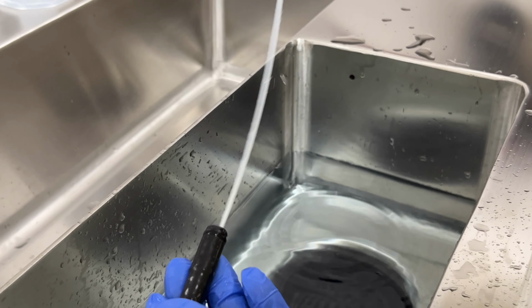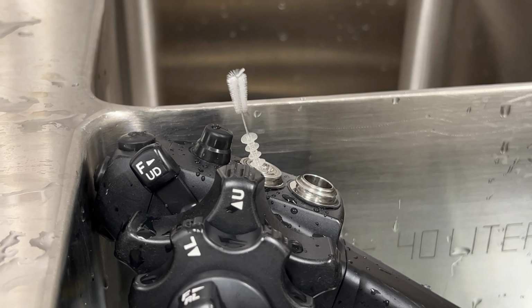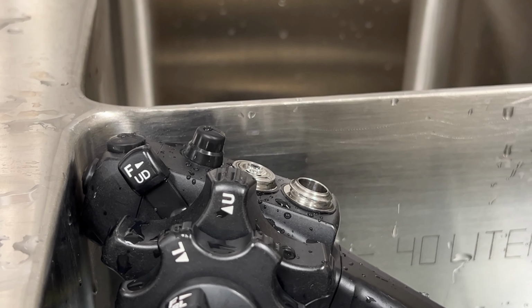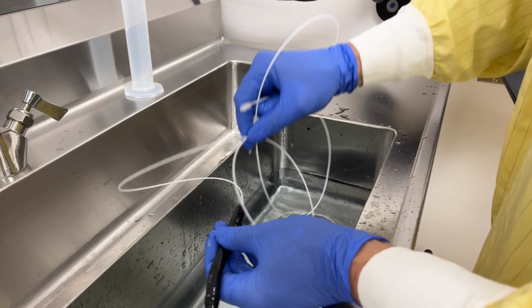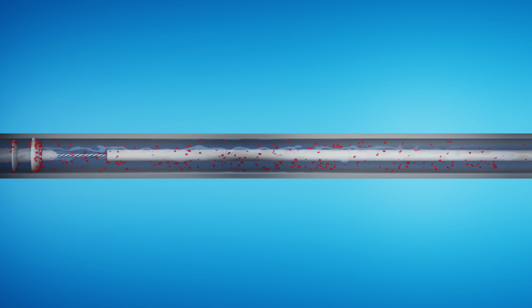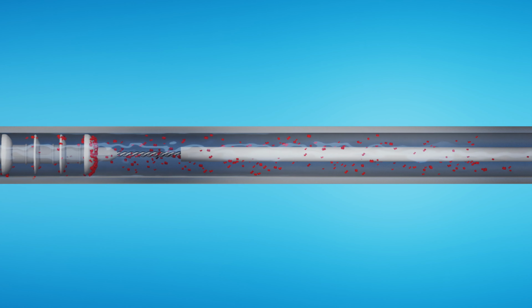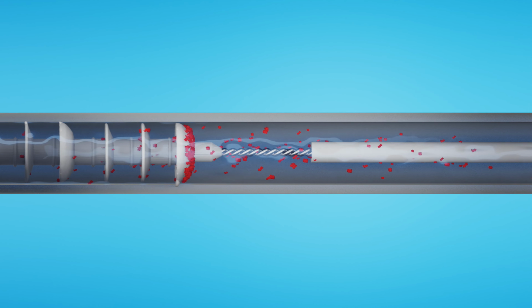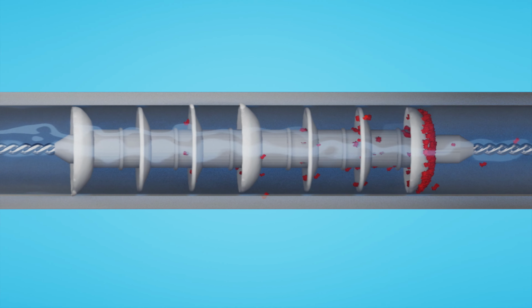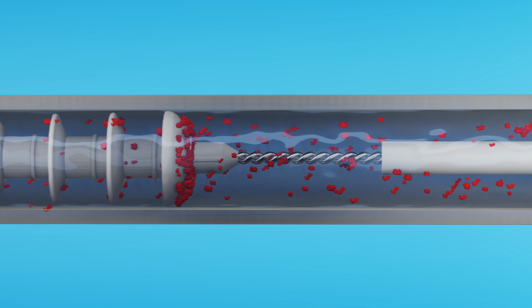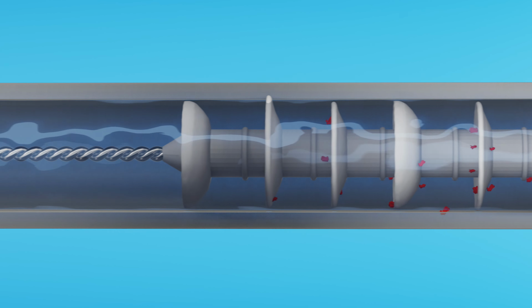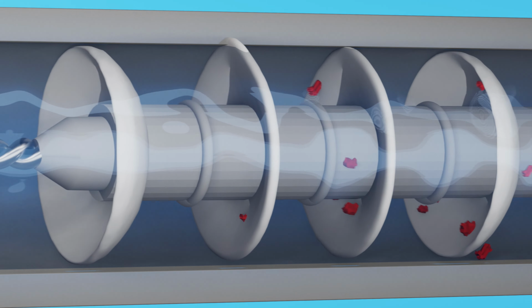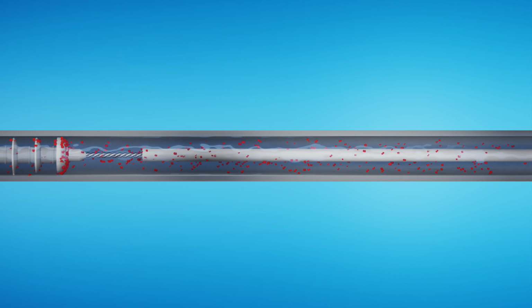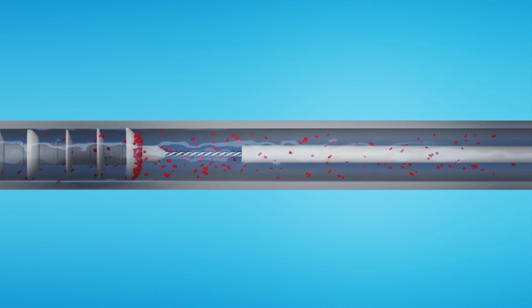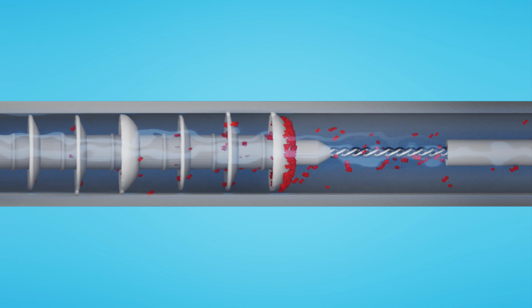The distal end of the SuperDART is pulled out, allowing the Squeegee multi-disc wiper and the tail brush to enter the endoscope's channel. The Squeegee multi-disc wiper effectively pushes down and removes the dislodged debris suspended in the enzymatic detergent solution and effectively swipes the channel wall. The multi-disc wiper is responsible for removing most of the bioburden from the channel. It also suctions in the solution from the wash sink, ensuring the channel is filled with it after the squeegee pass.